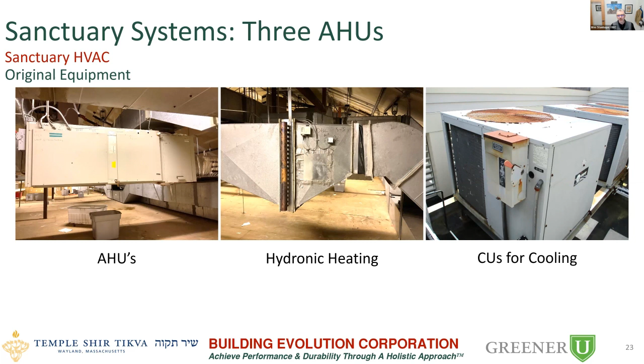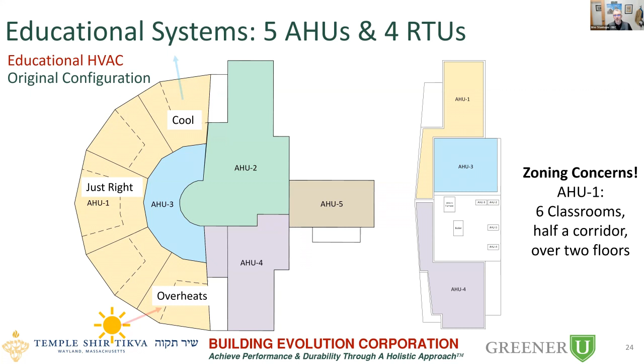Another thing about control: the left-hand side of this is the educational side of the ELC, and there are classrooms wrapping around the semicircular side of the building. In the morning, the sun comes up on the east side and will start to overheat some of the classrooms. But it's all zoned as one temperature control, one air handling unit. That same air handling unit also serves another zone in another part of the building. So if somebody has one thermostat right in the middle and their temperature is just right, you're going to have one space overheat and another space too cold because they're losing heat through their glazing. Not an ideal situation to try to keep multiple classrooms with children and teachers satisfied for temperature. So when systems are coming toward end of life, it's a good opportunity to look at what you can do differently.